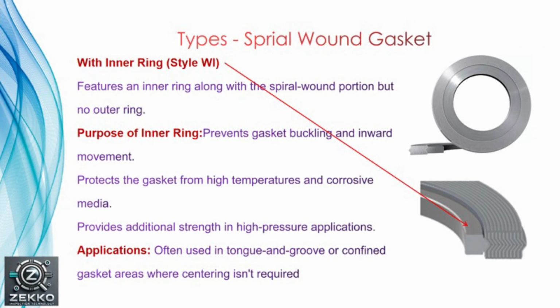The third type of spiral wound gasket is with inner ring. That is also called style WI. It has an inner ring along with the spiral wound portion, but no outer ring. There is no outer ring in this particular gasket. The purpose of the inner ring is to prevent the gasket from buckling and inward movement, and it also protects the gasket from high temperatures and corrosive media. It provides additional strength in high pressure applications. Basically, the application for this gasket is that it is often used in tongue and groove or confined gaskets where no centering is required. I have marked this inner ring with the arrow, so you will be very clear about where the inner ring is.